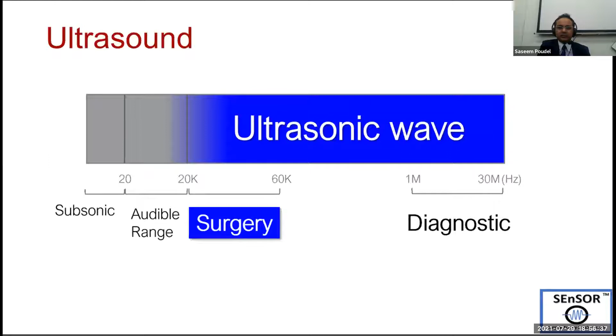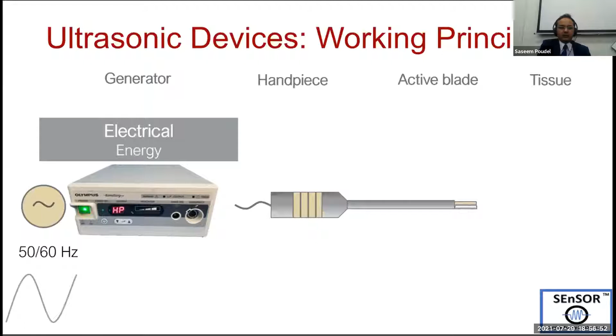In surgery, we generally use ultrasonic waves from 20,000 to 60,000 hertz. So what happens in the ultrasonic devices? This generator we have is basically similar to an electrosurgical unit. It takes electricity from the wall, that is 50 to 60 hertz depending on the country, and changes it to an ultrasonic frequency of 20,000 to 55,000 hertz, depending on the machines that various companies use.